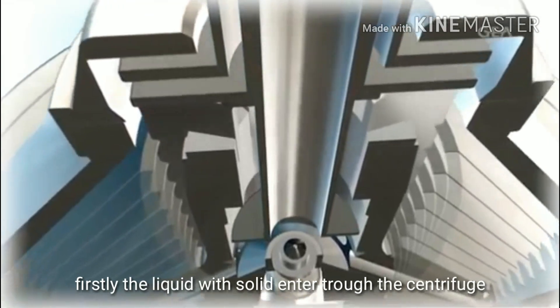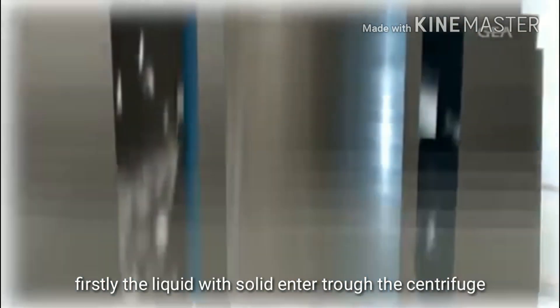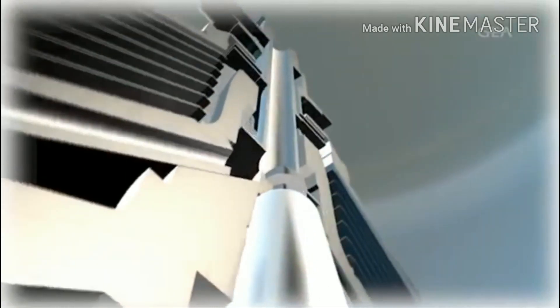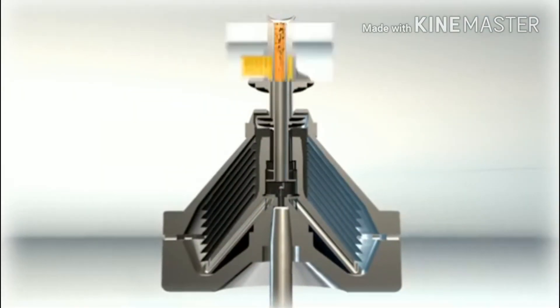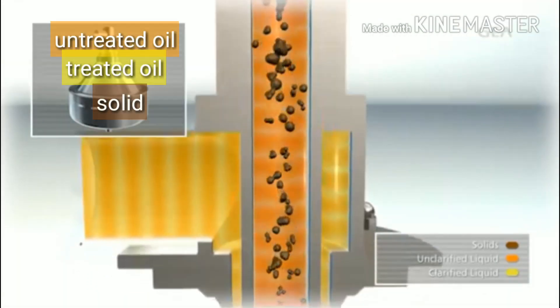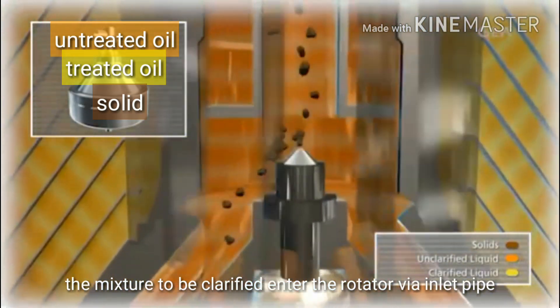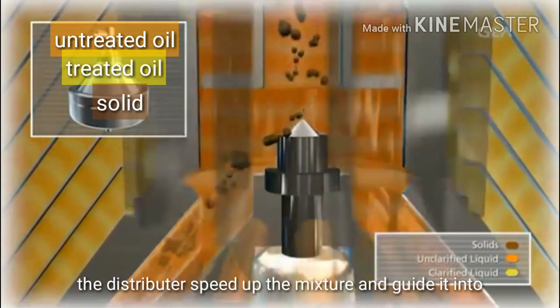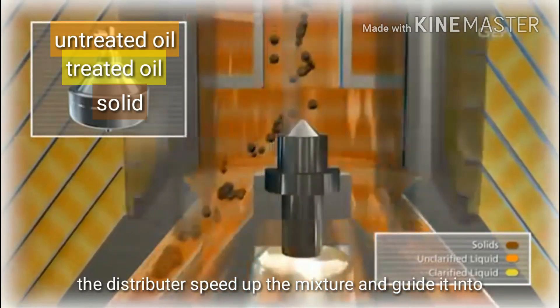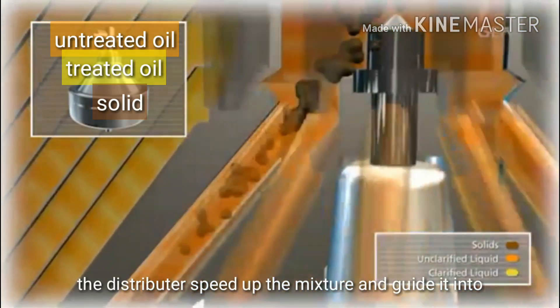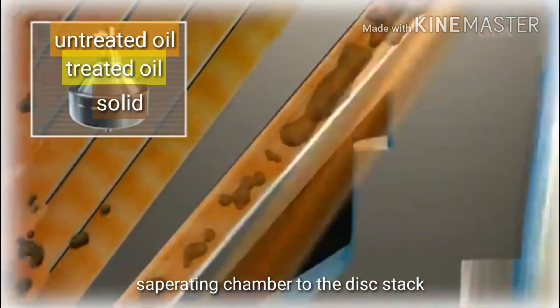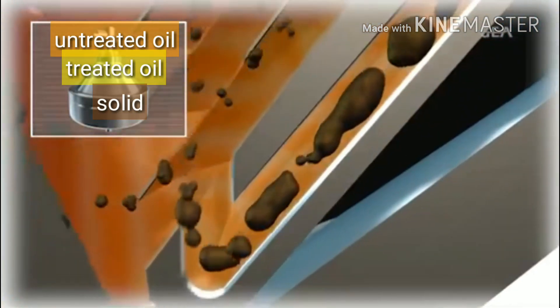In order to understand the entire function of a separator, we simply have to follow the path of a liquid loaded with solids through the centrifuge. The mixture to be clarified enters the rotor via a centrally positioned inlet pipe. The distributor speeds up the product and guides it into the separating chamber, the disc stack. This is where the actual separation of the solids and liquids takes place.